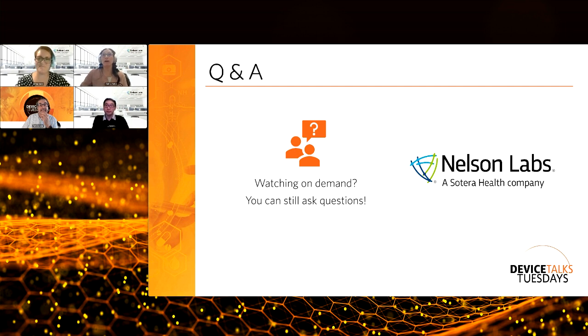So old biocompatibility certs can certainly give you some information, but I would be more curious about what has changed between the time of testing and the product that you have now. And when I think about certificates from suppliers, often they will say that it's a one-for-one change or like-for-like change. That may be the case from a supplier standpoint that meets their requirements, but from a biocompatibility standpoint, that is rare. So I would just ask questions. I'm not saying it's definitely not good. I would just be more curious and get more details on what has happened to the product since it's been tested.